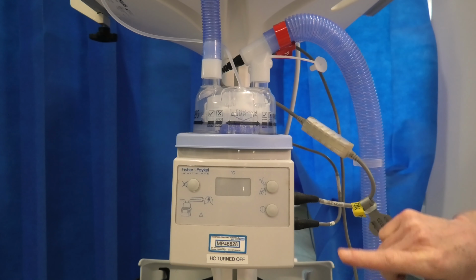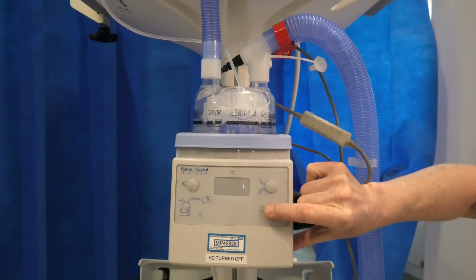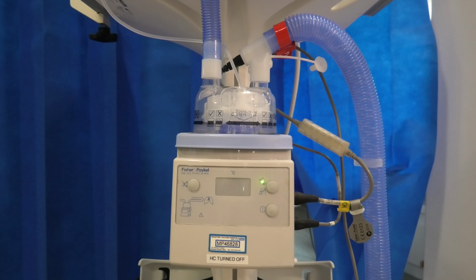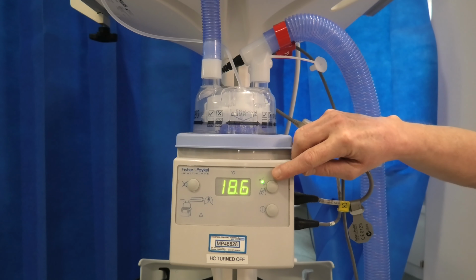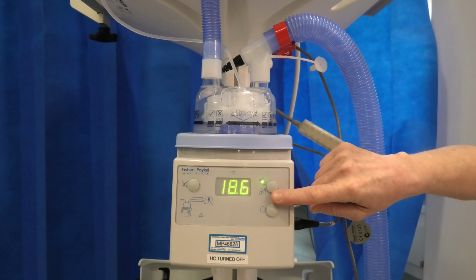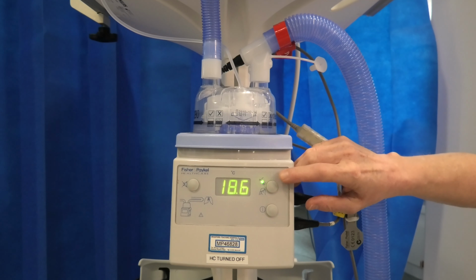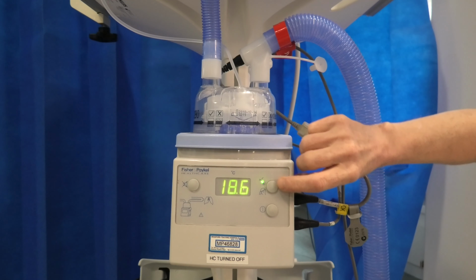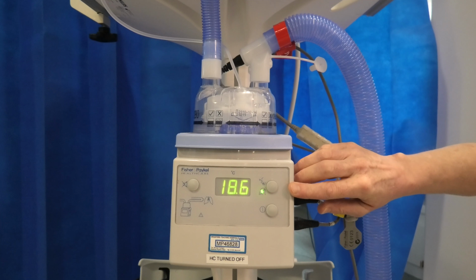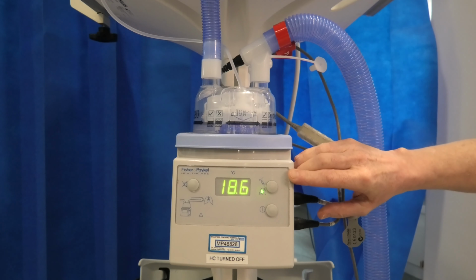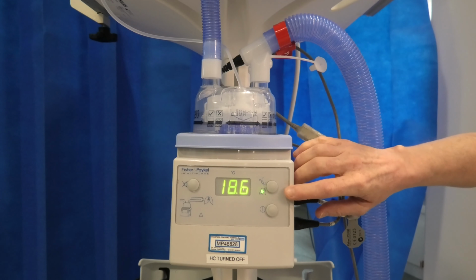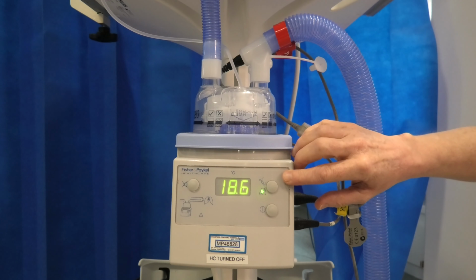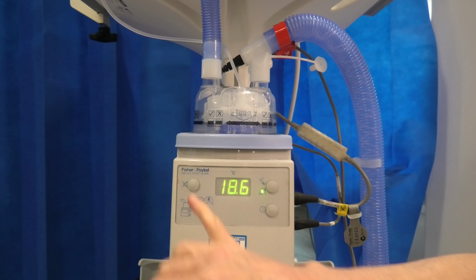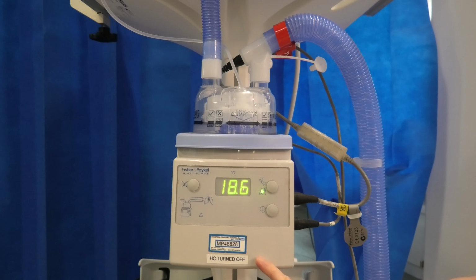Once you've set up your wet circuit, you need to turn your humidifier on. So if you press the bottom right hand button, here you can see you've got an ET tube setting, and here you've got a face mask setting. If you're using it in nasal high flow, it needs to be on the ET tube setting. If you're using it for CPAP, it needs to be in the face mask setting. The ET tube setting is hotter than the face mask setting. So if you try to do CPAP with it on ET tube, your patient won't be able to tolerate the higher temperature. This is your alarm silence button. If there's a problem, then there's lights that flash up, whether it's at the patient end or the machine end, and allows you to fix the problem.